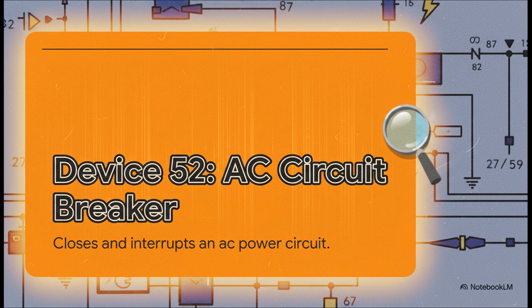The relays, like 50 and 51, they're the brains. They do the detecting. But it's the 52 breaker that gets the signal and then physically, mechanically opens the circuit to stop the flow of that dangerous current. It's what isolates the problem from the rest of the healthy system.